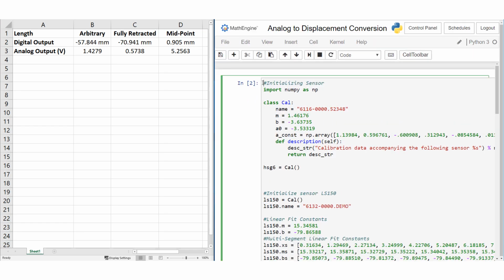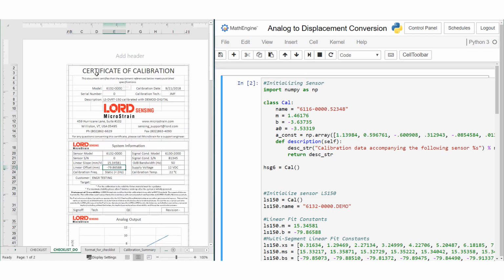In this first cell, I am initializing all of the calibration data, which can be found on the certificate of calibration. No sensor and signal conditioner pair is shipped from our facility in Vermont without one of these certificates. You can see here that the linear slope is almost 15 millimeters per volt, while the offset is about -79 millimeters, which I entered into Python right here.